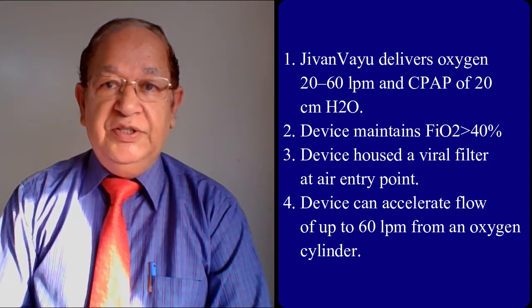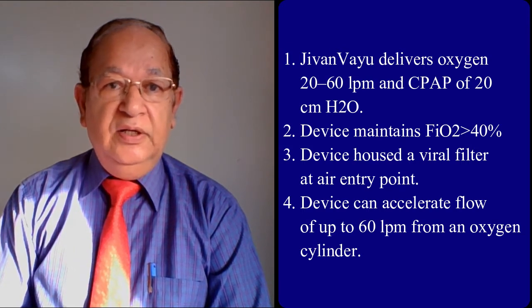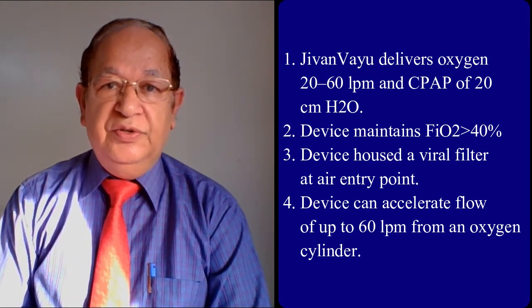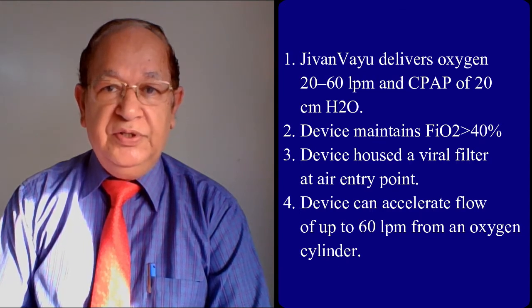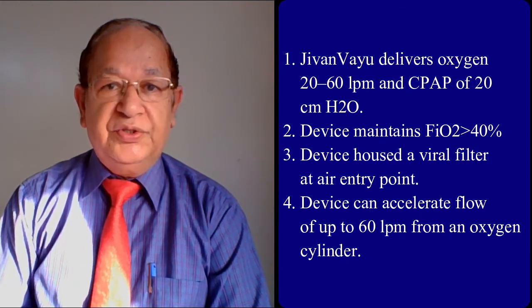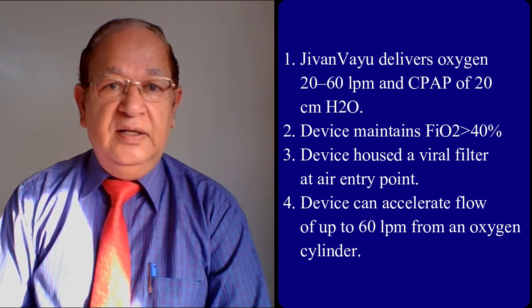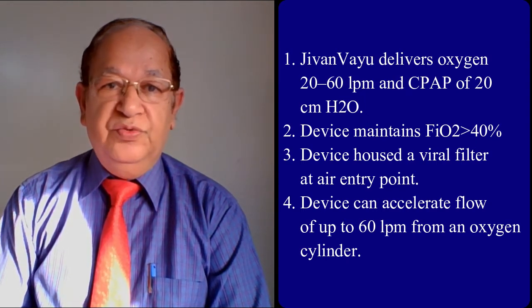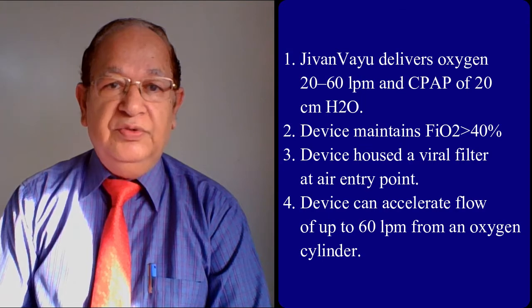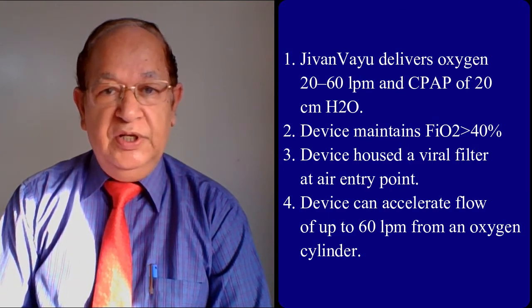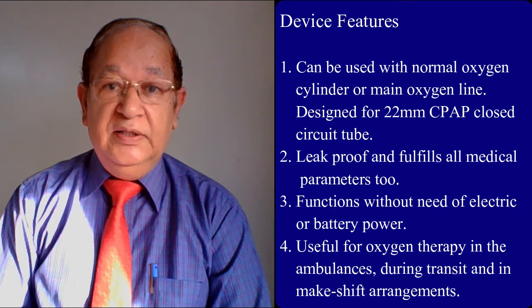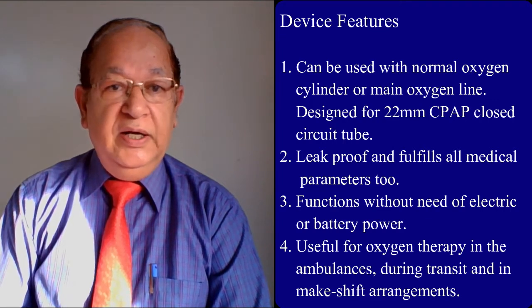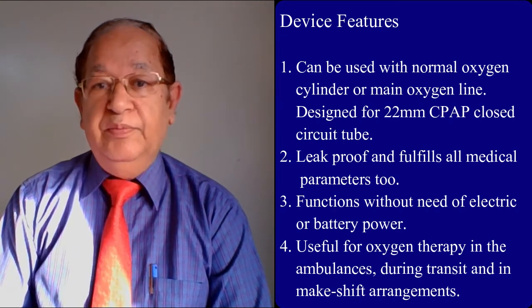Additionally, the device houses a viral filter at the air entrainment with a viricidal efficacy of 99.99%. The viral filter ensures that the entrained air does not bring in any pathogens from the environment. The design specifications have been modeled to optimize an accelerated flow of up to 60 liters per minute from an oxygen cylinder, and the device has been produced by additive manufacturing using 3D printing.